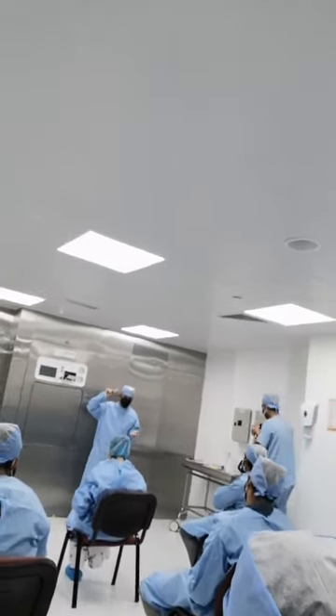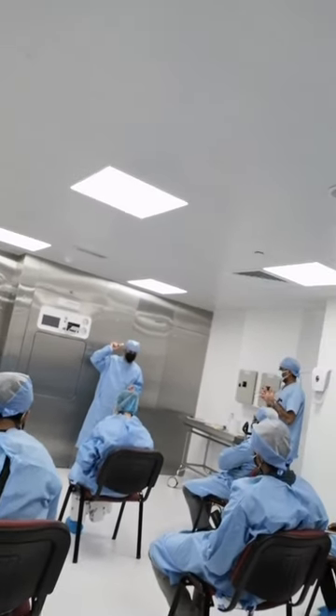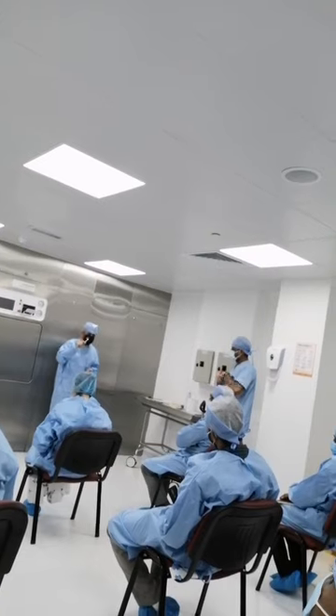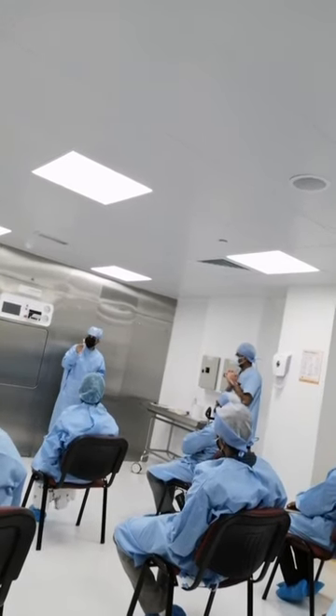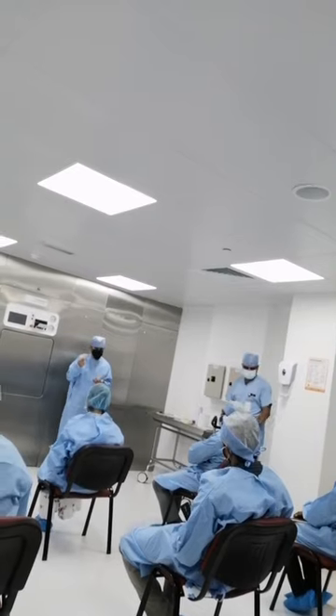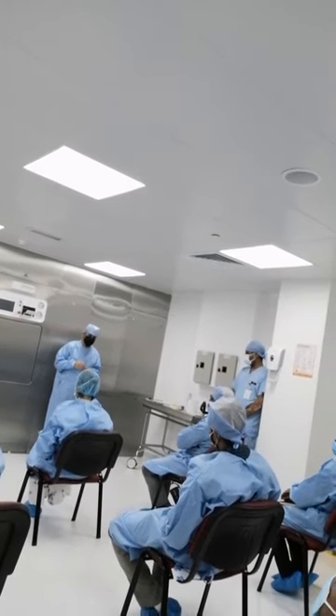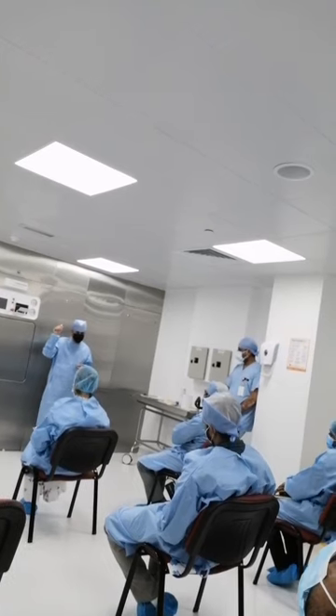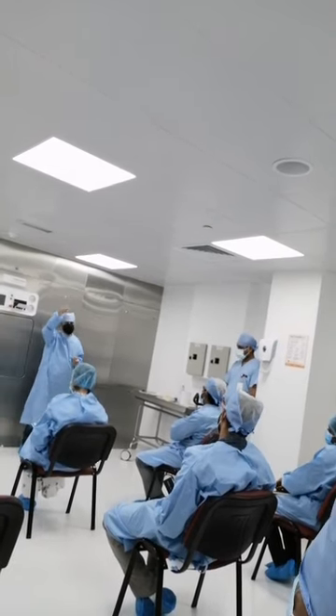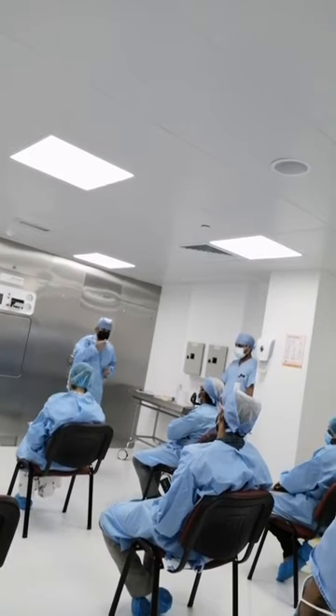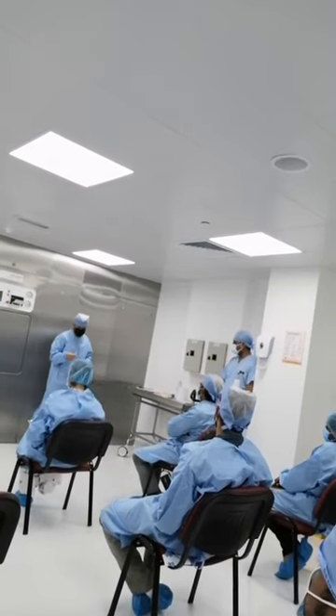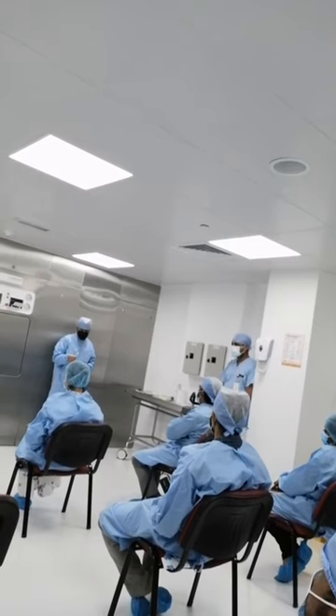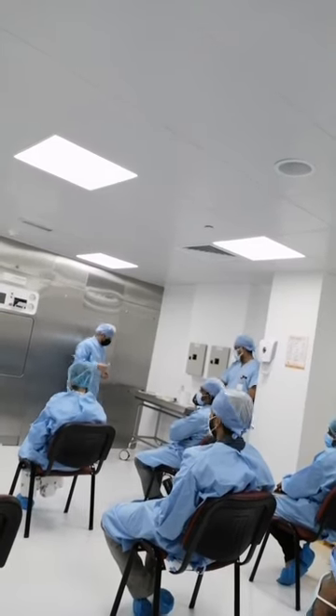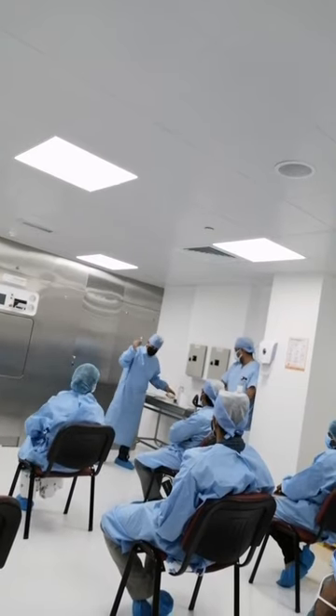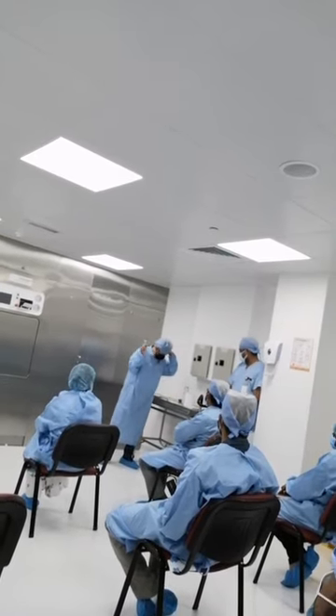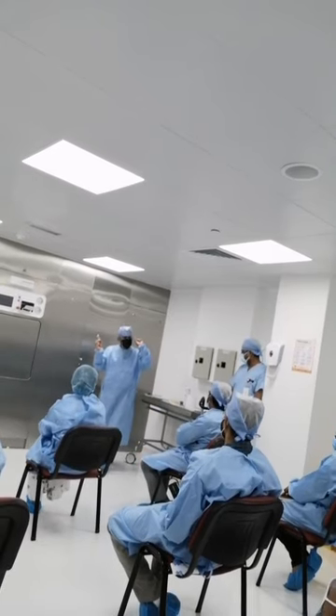According to the recommendation from CDC, this has to be done weekly, preferably daily, and with every implant. So that's why you are always searching for the fastest biological indicator, so you release the load fast and give it to the OR, especially if it has any kind of implants. So that's why it was 48 hours, 24 hours, and then 3 hours, and then 1 hour, and then sometimes even about 20 minutes. This is great. This is the latest. Okay. Very common. I will tell you, in fact, this is the American school. This is the American school. Okay? Europe, they are not using this.